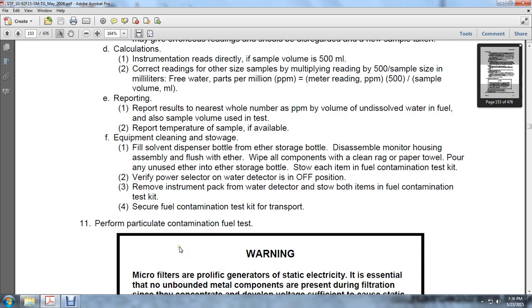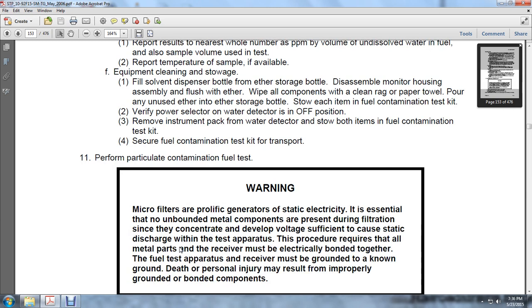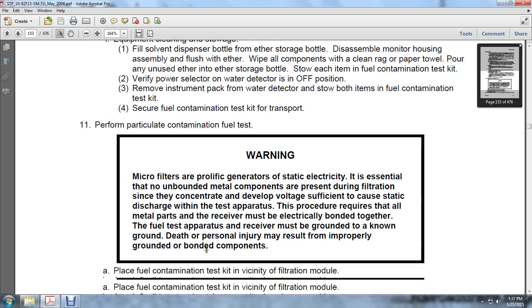11. Performing a fuel contamination test. A microfilter is a prolific generator of static electricity. It is essential to bond all metal components present during filtration, since the voltage developed is sufficient to cause static discharge with the test apparatus. The procedure requires that all metal parts and the receiver be electrically bonded together. The fuel test receiver must be connected to a known ground. Death or personal injury may result from improper grounding of the bonding components.